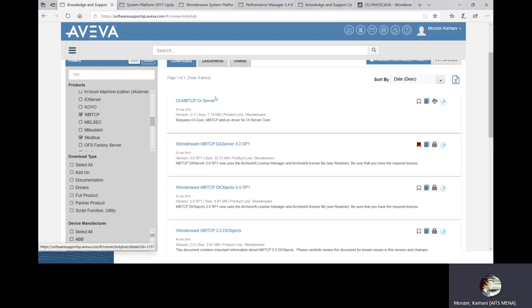That means I have one server and different drivers here. The whole server comes together with the driver. This is one of the functional differences. You can see from the difference how the size is. Then the licensing: the new drivers need XML licensing with activations, and we'll talk about the activation briefly later on. The DAS server only needs the .lic licensing, the ArchestrA License Manager. Those are both, but the configuration is together.